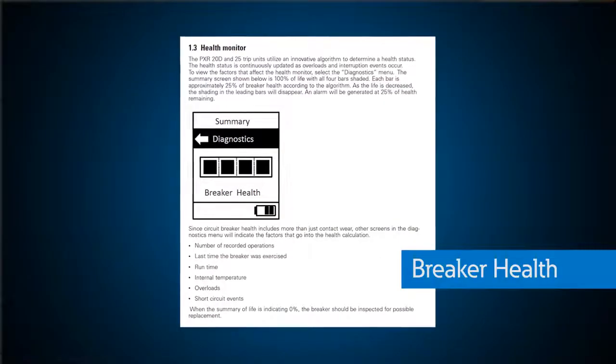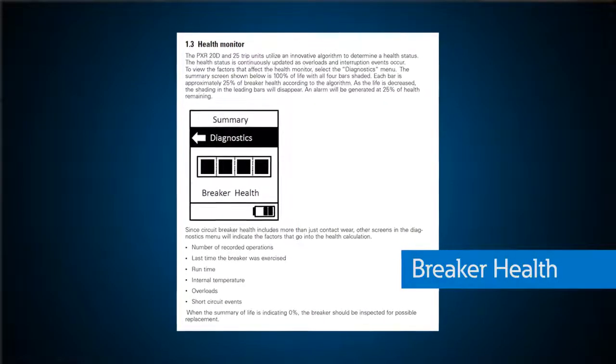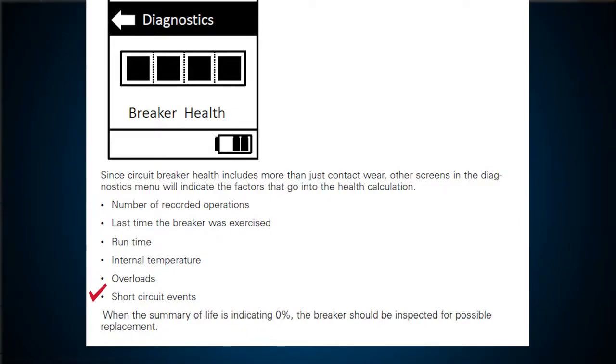The good news is that Eaton is full of experts that have analyzed how differing conditions affect molded case circuit breakers over time for several years. Power Defense molded case circuit breakers with PXR trip units offer a unique feature called breaker health. Breaker health empowers the trip unit to monitor conditions that affect the health of the breaker, such as overload events, short circuit events, breaker operations, or how many times the breaker is turned on and off, when the last operation took place, how long the breaker has been in service, and the internal temperature of the breaker. All of these metrics are combined with a proprietary algorithm to provide a metric showing the health of the breaker.